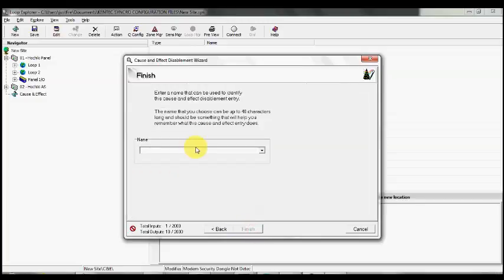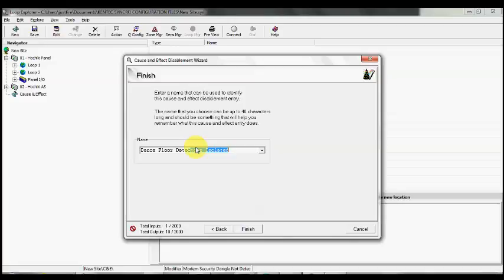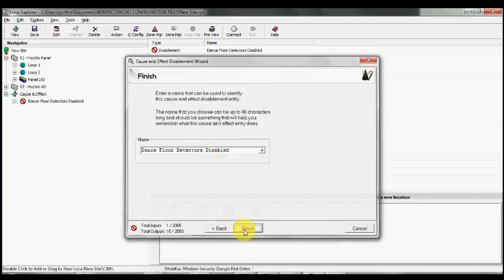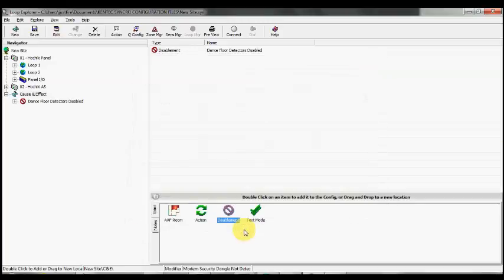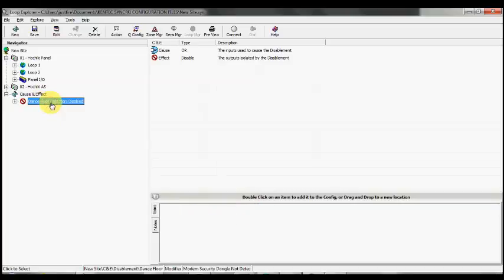Go next. Now assign some text so that when we turn that key and it operates that input, it will come up on the front of the panel with some text as to what's occurring. There'll be a disablement light on the panel, and it will show this message. Say finish, and there we go. That's now created—there's our cause and effects line.